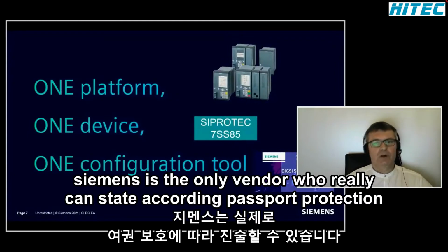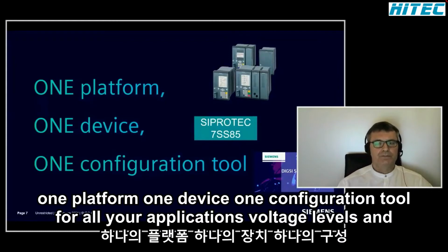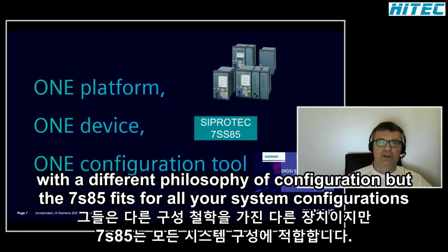Siemens is the only vendor who can really state this for busbar protection: one platform, one device, one configuration tool for all your applications, voltage levels and busbar protection schemes. Thinking about, e.g., ABB, they have the REP 670 for the centralized busbar protection and the REP 500 for the distributed busbar protection. They are different devices with a different philosophy of configuration. But the 7SS85 fits for all your system configurations.